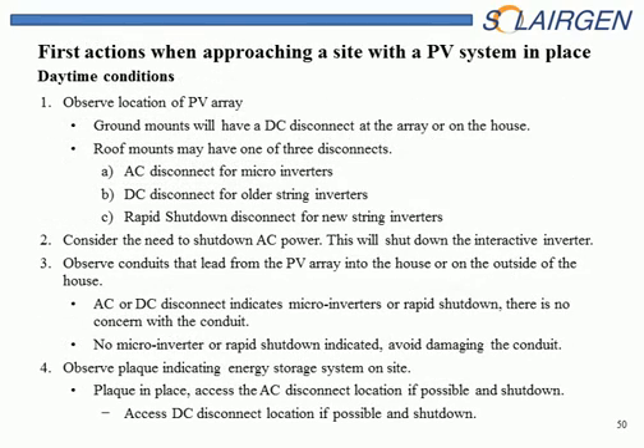First actions when approaching a site with a PV system in place. Daytime conditions. Observe the location of the PV array. Ground mounts will have DC disconnects at the array or on the house. I doubt if there's any PV systems that actually have the DC disconnect in the house if the PV array is outside.